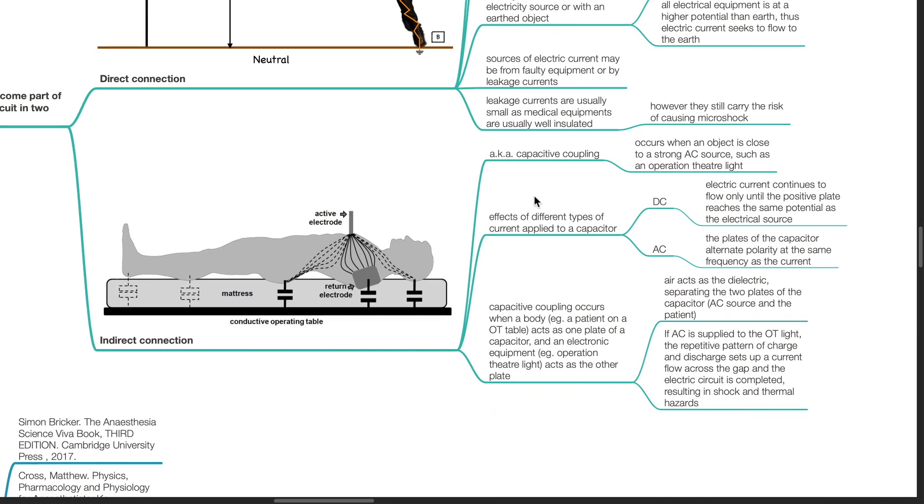Indirect connection, also known as capacitive coupling, occurs when an object is close to a strong AC source, such as an operation theater light. Effects of different types of current applied to a capacitor: for DC, electric current continues to flow only until the positive plate reaches the same potential as the electrical source. For AC, the plates of the capacitor alternate polarity at the same frequency as the current.